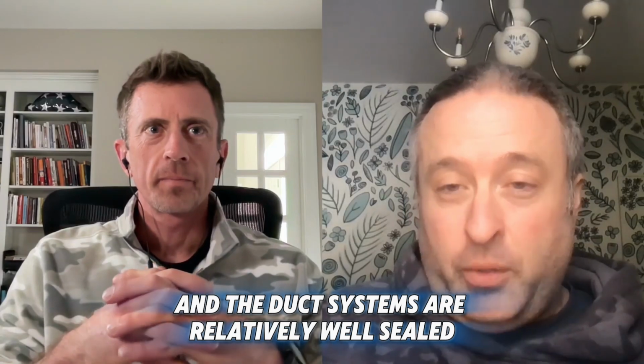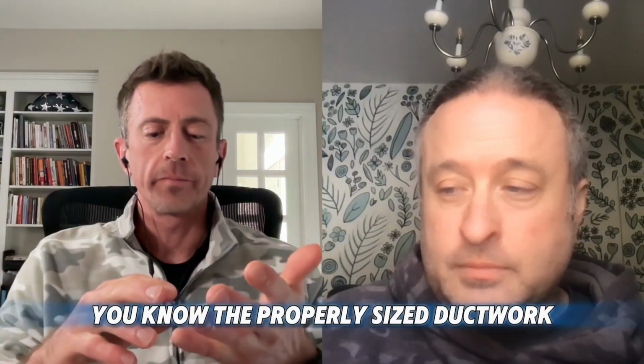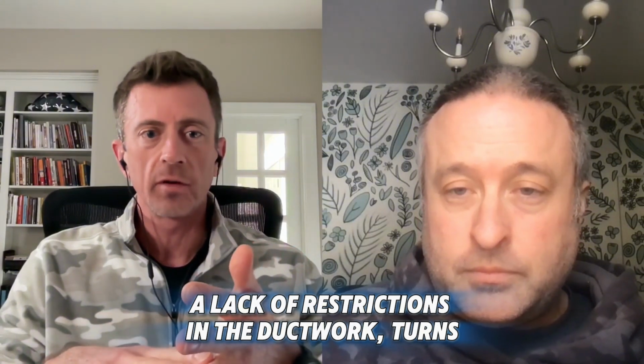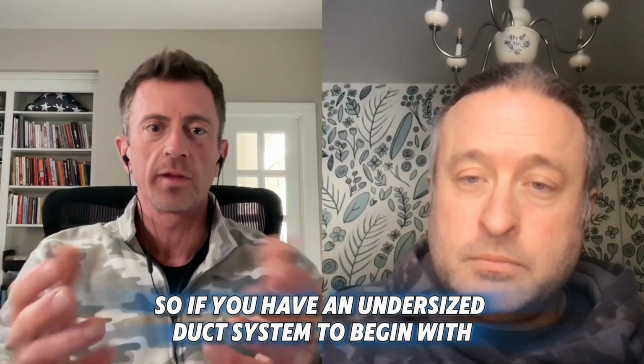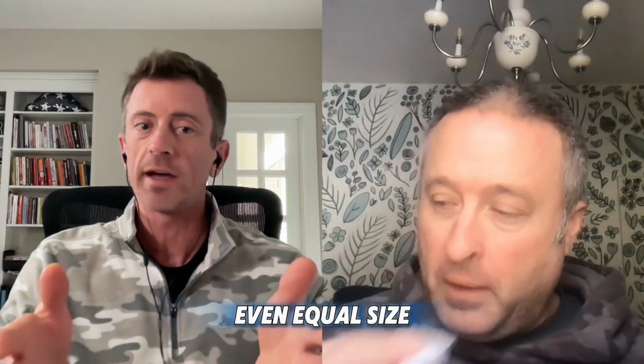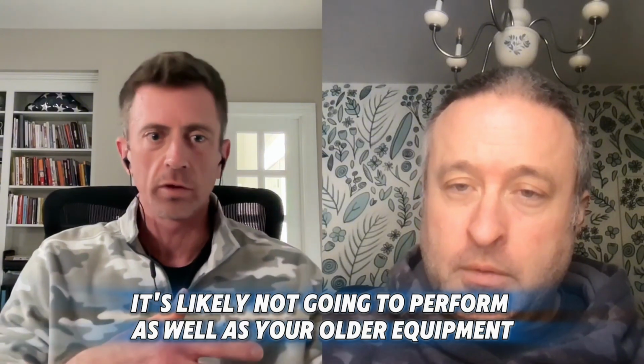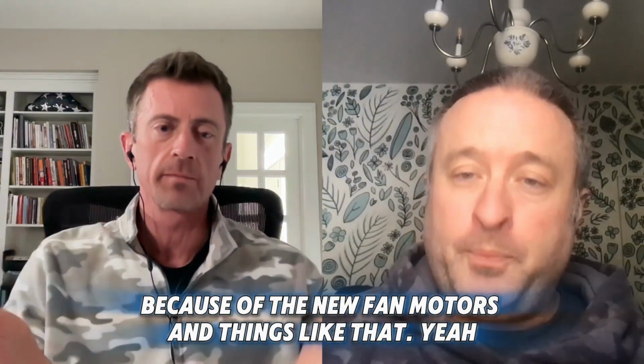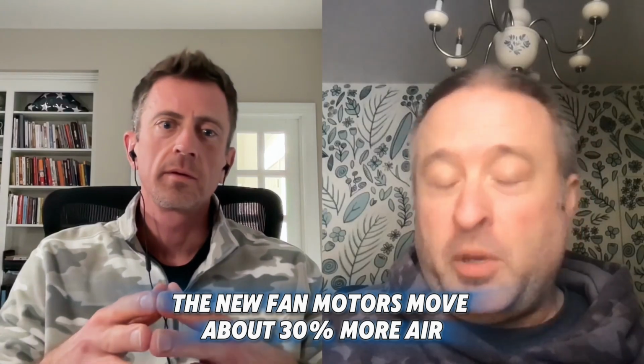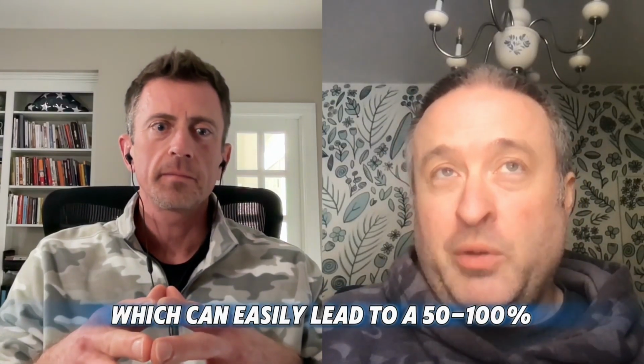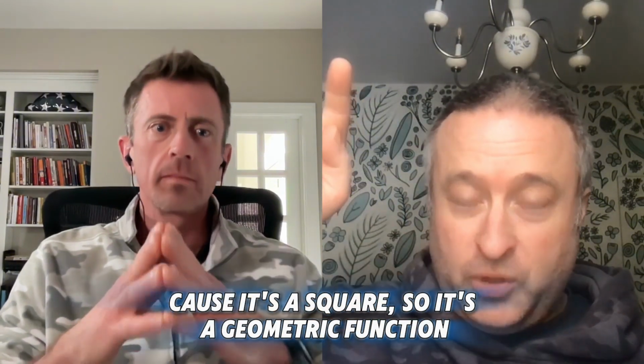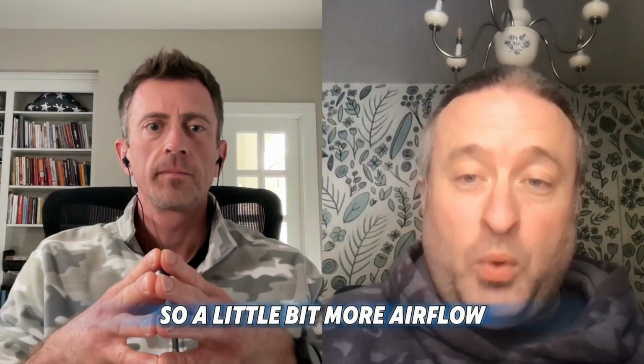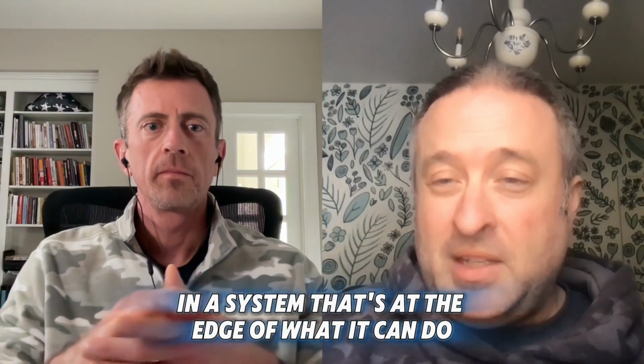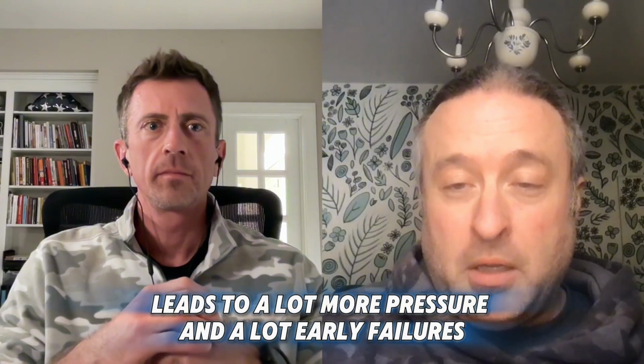And the duct system's relatively well sealed. And again, that all requires the properly sized ductwork, a lack of restrictions in the ductwork, turns, bends, all that stuff has to be accounted for. So if you have an undersized duct system to begin with, and you replace the equipment with something that's even equal size, it's likely not going to perform as well as your older equipment because of the new fan motors and things like that. Yeah, the new fan motors move about 30% more air, which can easily lead to a 50 to 100% increase in duct pressure. Because it's a square, so it's a geometric function. So a little bit more airflow in a system that's at the edge of what it can do leads to a lot more pressure and a lot of early failures.